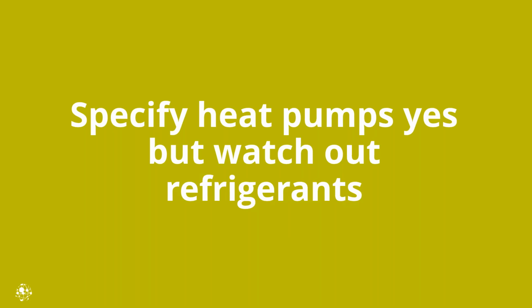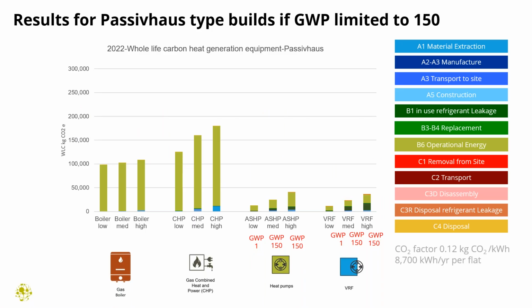watch out really for refrigerants, and we really need regulation to become a bit stronger on this, because at the moment the F-gas regulation in Europe is trying to mitigate the environmental impacts of refrigerants, but it's really not enough. And the 150 target doesn't apply to the building industry yet. I mean, it only applies to really big commercial supermarkets.